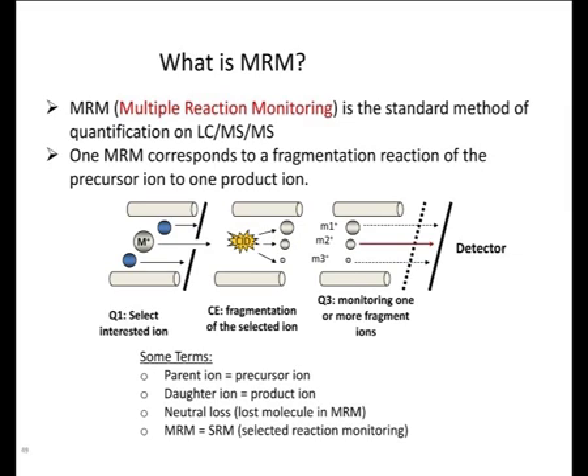Okay, how does it work? In MRM, you select the particular compound, or ions of particular peptides, in the first quadrupole. It goes to the second quadrupole, where it undergoes fragmentation, and you select only those product ions that have the highest intensity. That means here Q1 and Q3 are both in the SIM mode. Okay.